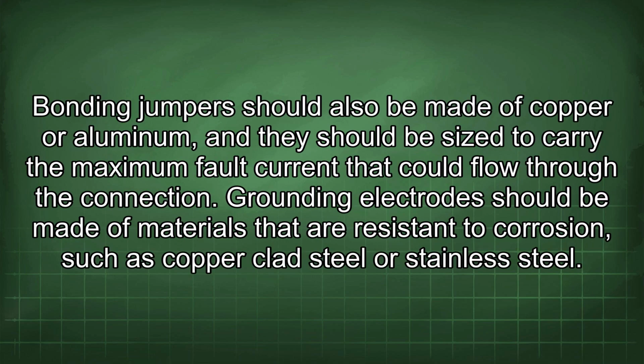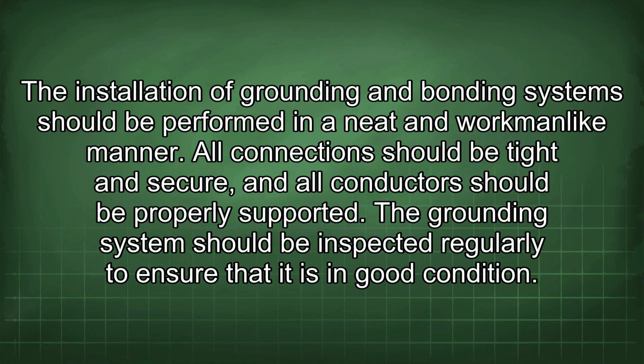Bonding jumpers should also be made of copper or aluminum, and they should be sized to carry the maximum fault current that could flow through the connection. Grounding electrodes should be made of materials that are resistant to corrosion, such as copper-clad steel or stainless steel. The installation of grounding and bonding systems should be performed in a neat and workmanlike manner. All connections should be tight and secure, and all conductors should be properly supported.